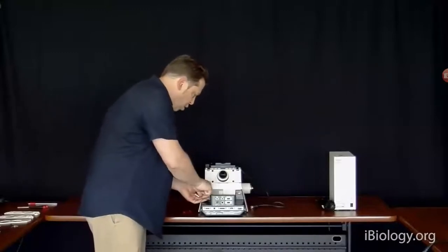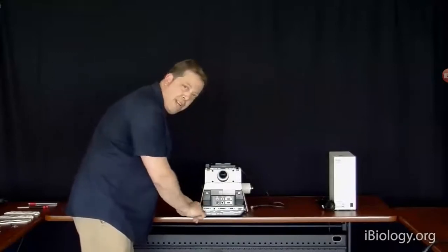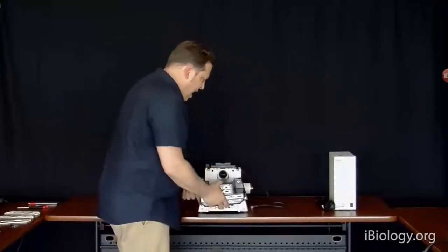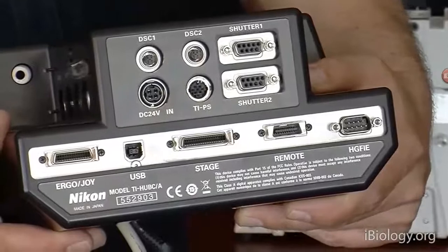Okay. This is what we call the hub controller on the microscope. And basically, it's the brains of the microscope. It takes all of the components in the microscope that are motorized and synchronizes them and controls them. And what we would do normally is with our software, send a recipe for an experiment, say, take one channel image, move a filter, take another channel image, move another filter, and so on, opening and closing shutters for transmitted light, epifluorescence light. And we can send all that information to onboard memory storage within this hub controller.